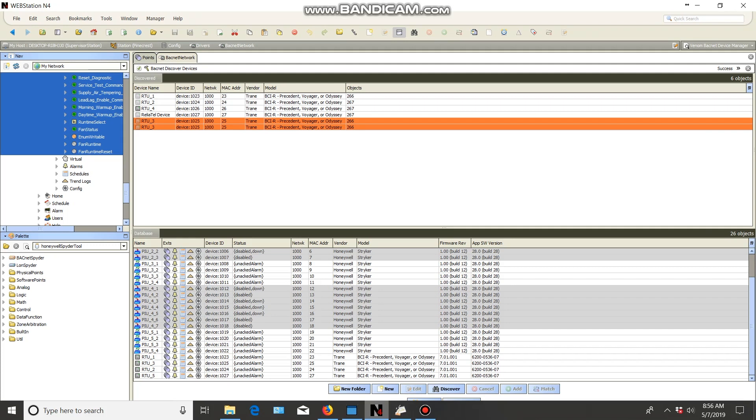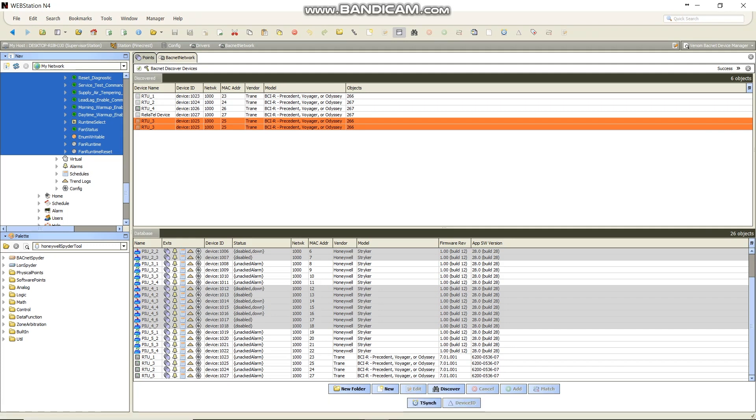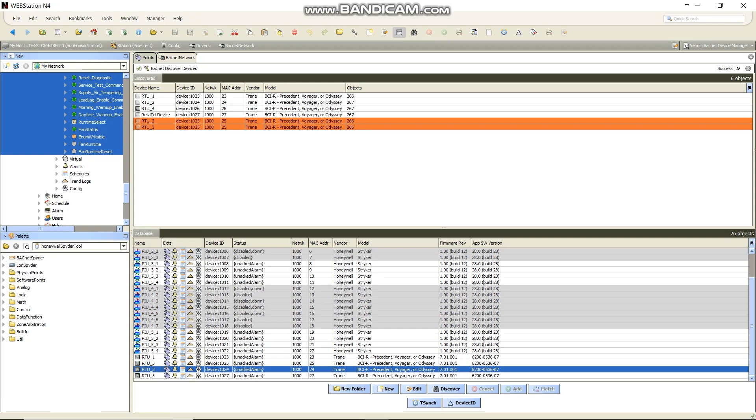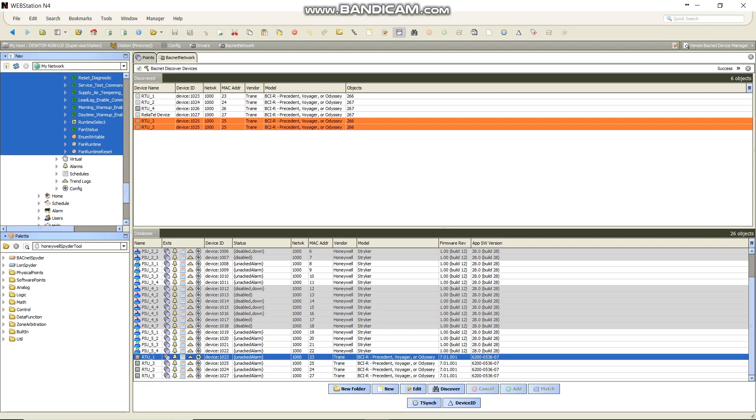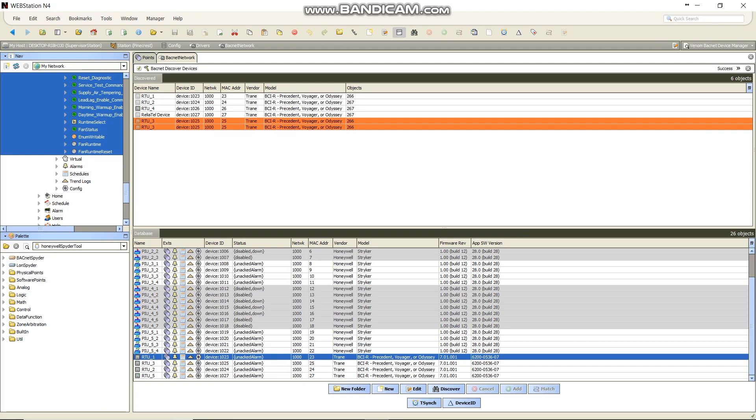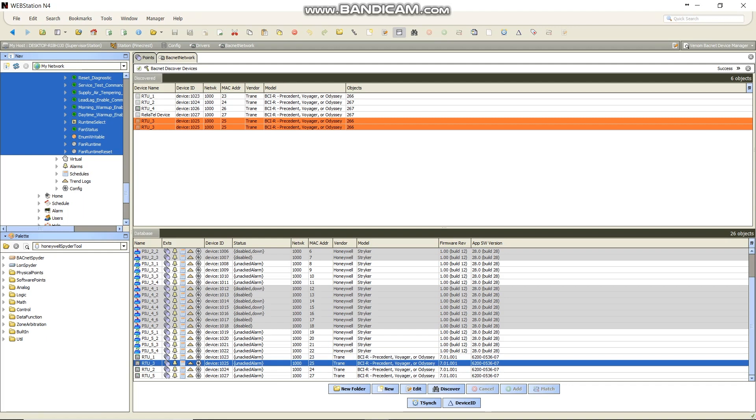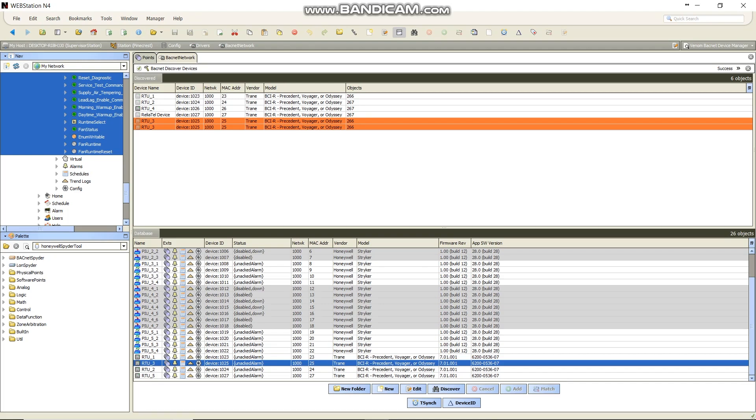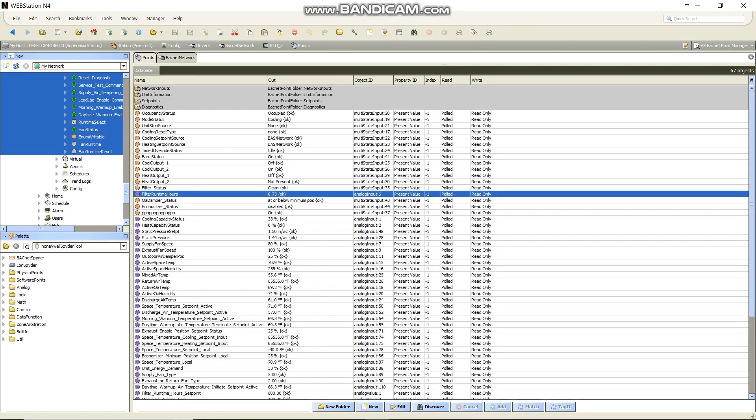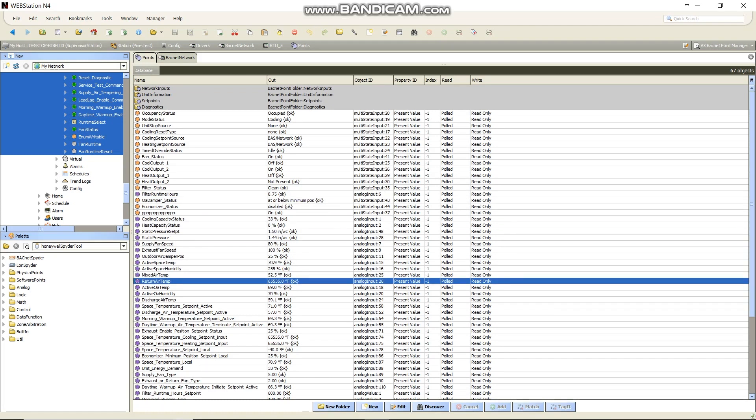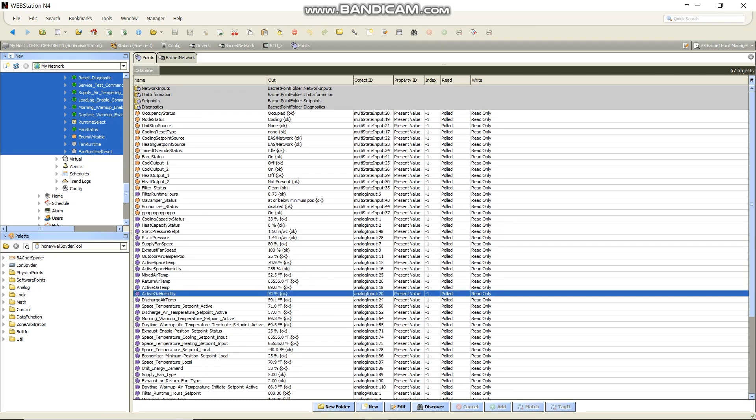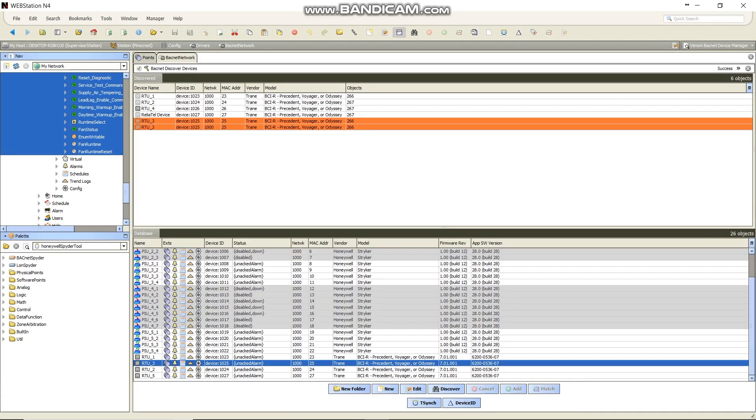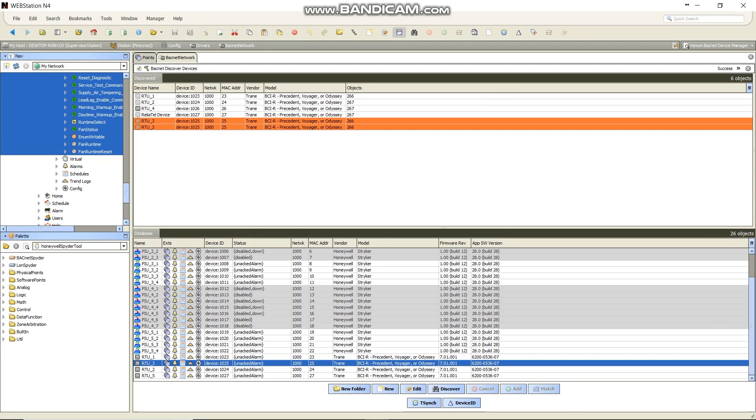All right, so the issue we're having, I mentioned, was with unit conversion. You can see down here that I've got all of these rooftop units pulled in, and they all look like they're the same in Trane, BCIR, Precedent, Voyager, or Odyssey. So one of the units that everything's going great with is this number five. You can see all these points pulled into here. Everything looks pretty normal. Space temperature setpoint, discharge air temp, discharge air setpoint.